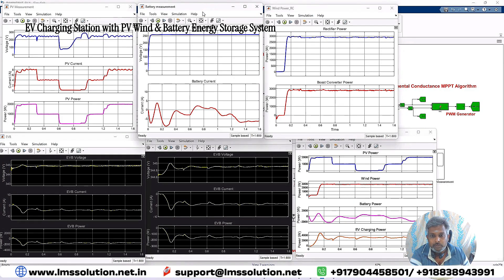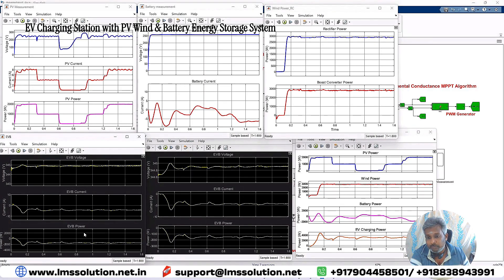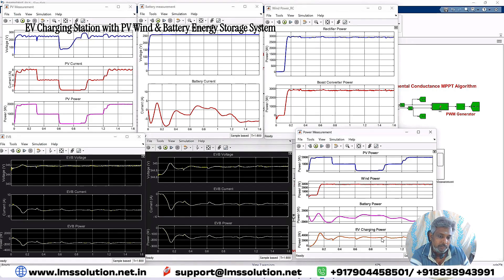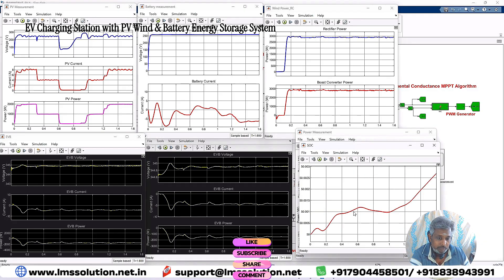Initially the storage battery goes for charging; from 0.6 to 1 seconds it discharges, then from 1 to 1.6 seconds it comes back to charging because of excess power available in the system. The EV voltage, current, and power show EV charging happening at around 1.5 kilowatt for both EV batteries. Looking at the combined power: PV power, wind power, battery power, and EV charging power — the accumulated power of 2 EV batteries charges at around 3 kilowatt constantly. The storage battery power goes for charging and discharging according to the power generation from PV and wind.